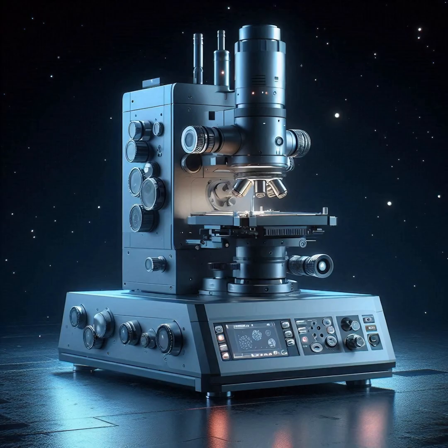When all parts of the detector are used to collect electrons symmetrically about the beam, atomic number contrast is produced. However, strong topographic contrast is produced by collecting backscattered electrons from one side above the specimen using an asymmetrical directional BSE detector.